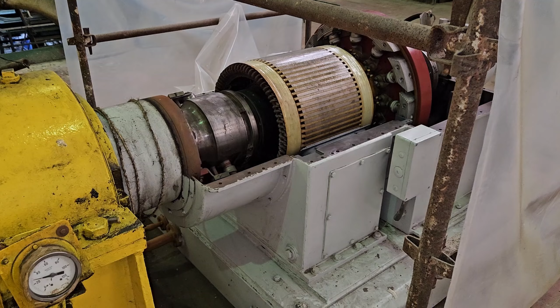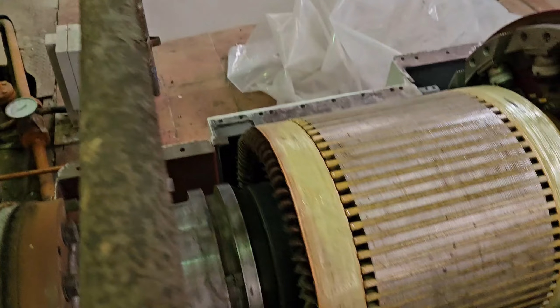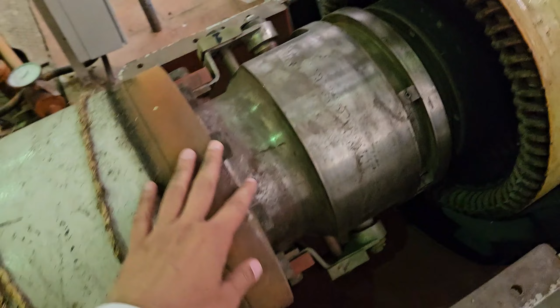So now let me show you the exciter. Here we have the rotor of the exciter. This is the complete exciter, and this is the rotor of the exciter. This is the stator of the exciter. The top cover has been removed for maintenance, and this is called the diode wheel. Here you can see these are the diodes, and this is the heat sink for the diodes. This rotor is connected with the generator rotor through these links. This is the coupling point of the generator and exciter.